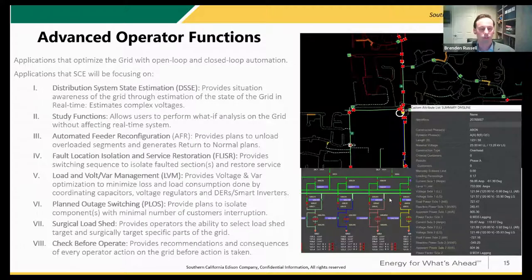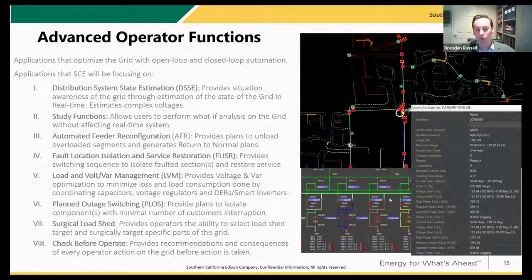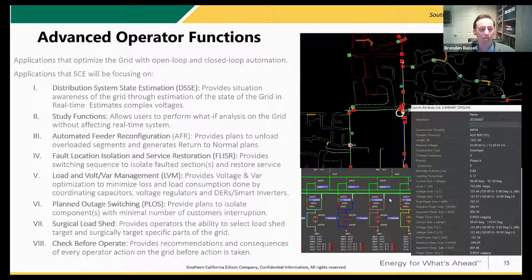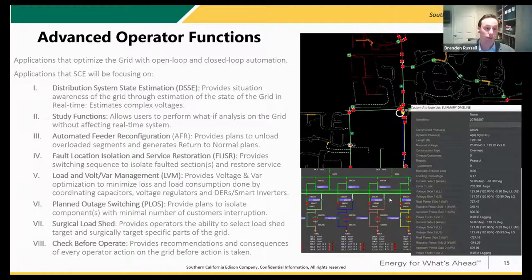The next category is what we call advanced operator functions. Things like PLOS — Planned Outage Switching — which allows the operator to select a device and it will automatically develop a switching plan. What could take two hours could be done in 10 to 20 minutes. Surgical load shed, check-before-operate — a lot of these functions provide additional safety checks and recommendations to the operator before any action is taken. And then LVM, which is going to replace our legacy volt/var application — allowing us to control cap banks, voltage regulators, and smart inverters, coordinating all their operations to optimize voltage and var.